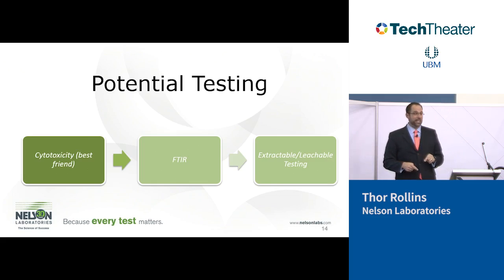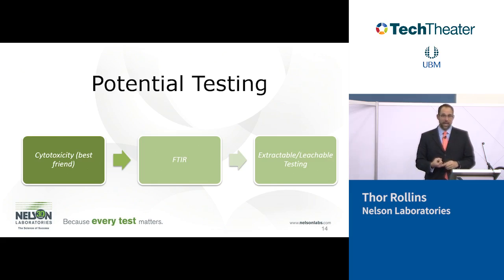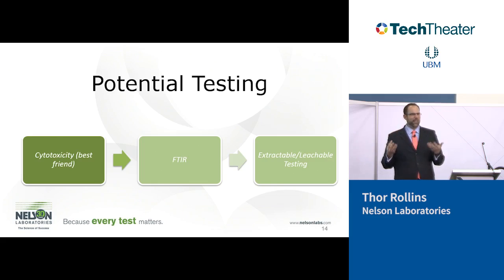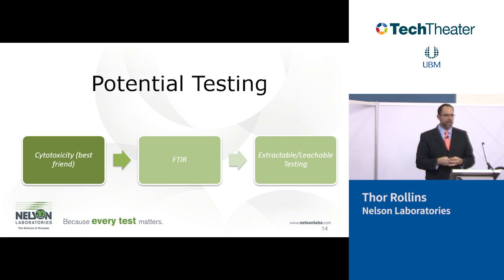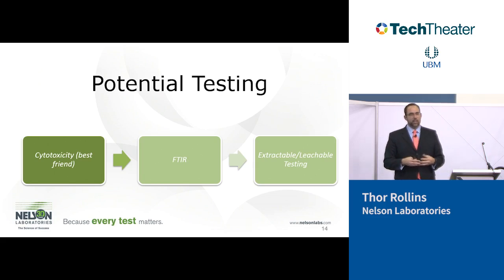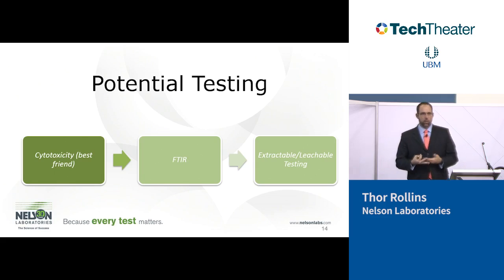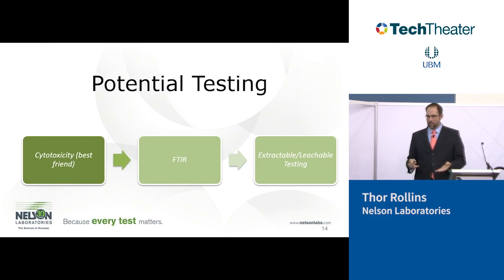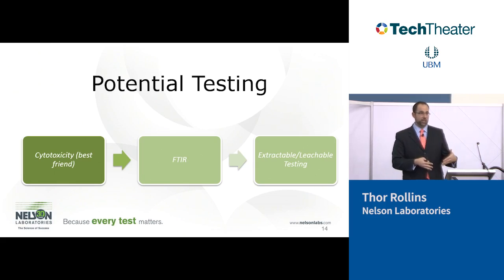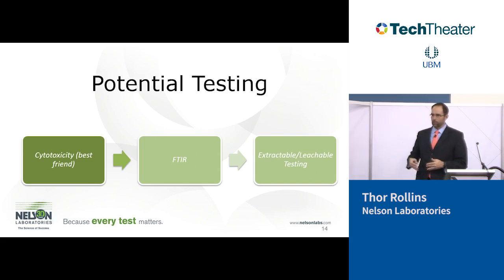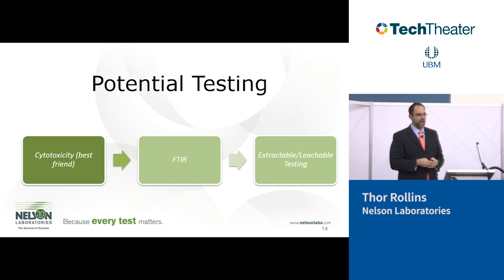But it's your best friend because it's extremely cheap and quick. At Nelson Labs, it's about $165 to do a non-GLP cytotox test and it takes 5 days. So you've got the most sensitive test, but it's the quickest and cheapest. It makes it great for screening changes of a medical device. Another test that we use is FTIR.